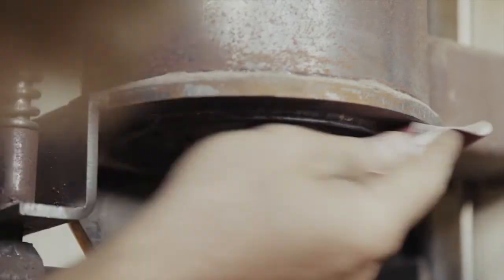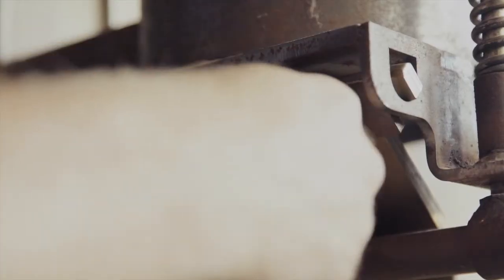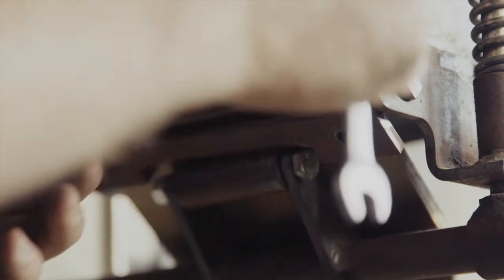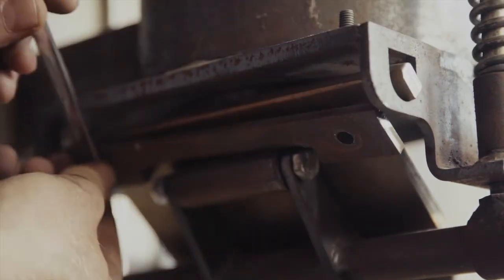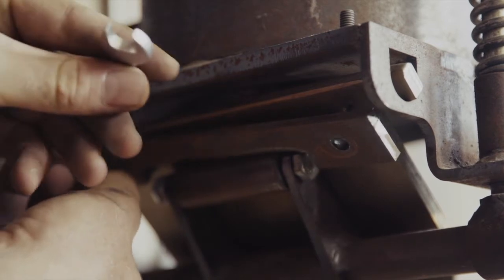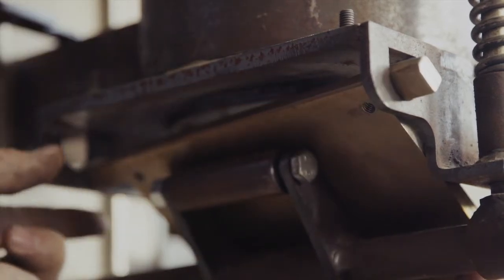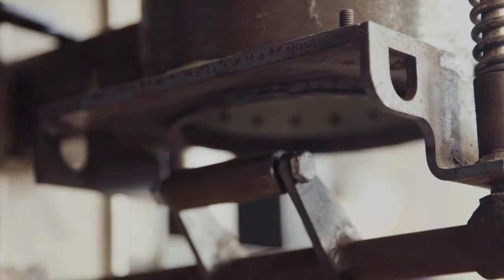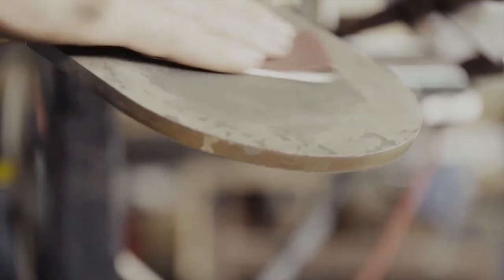On occasion it may be necessary to remove the burner plate completely. To remove the plate, there is a spacer bolted to the underside of the plate with two bolts which need to be removed. Once the spacer is removed, the plate can slide to the side to allow the other side to be removed from the pivot point. The plates can then be fully cleaned and there is also full access to the sealing ring surface on the burner nearest the pivot point.